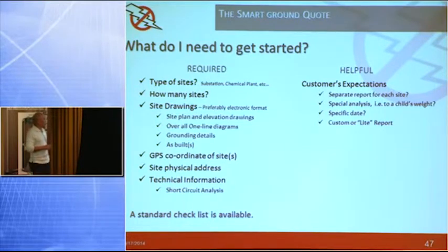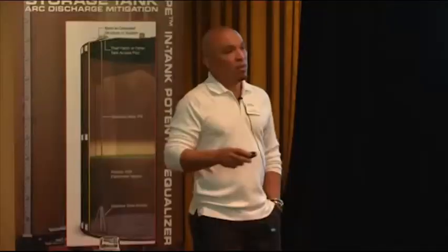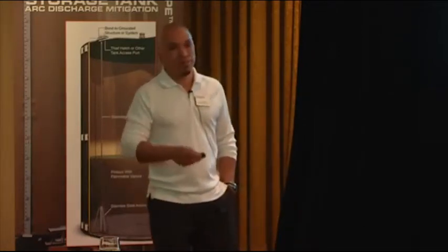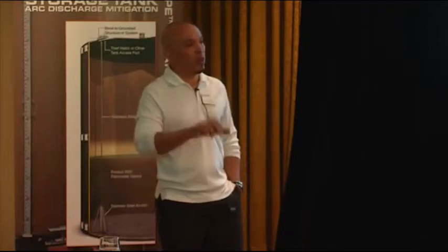Technical information, if they have a short circuit analysis. And then helpful is, what are the customer's expectations? What are they trying to find out? Are they just doing this for insurance purposes where they have to get a test done every 5 years? Or is this something with litigation? That's why I put in there, are we doing something specific, even to a child's weight, to determine what had happened to somebody smaller than a standard human being? Usually the testing for IEEE Standard 80 and IEC is relegated to a 50 or 70 kilogram person. So, somebody much larger than a child, where their body resistance is not as high, and their susceptibility to a fault is much greater.